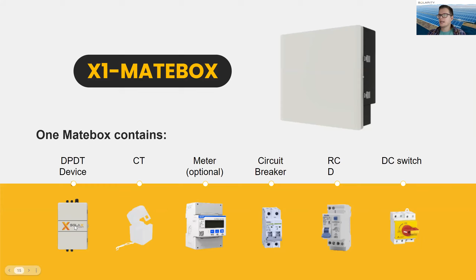So the DPDT device, or we call it EPS box, we use it to make sure that the installation will work properly during the blackout. So if you have a power outage, this device ensures the energy supply of all your facility, not just one electrical circuit, right? But the entire power of your entire facility. It's an electromagnetic device. On the internet, it says that it integrates two contactors which provide power steering for users. So actually, it switches the circuits between the inverter circuit and the battery circuit. So if you want your system to work during the blackout, during the power outage, this device is critical.